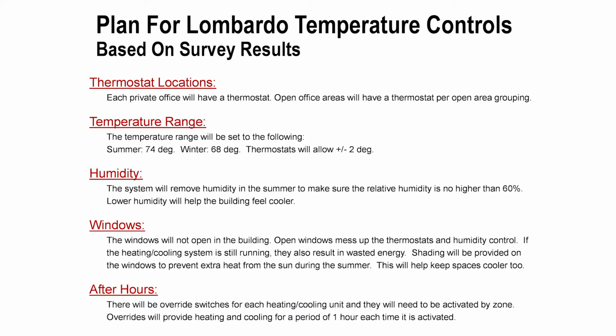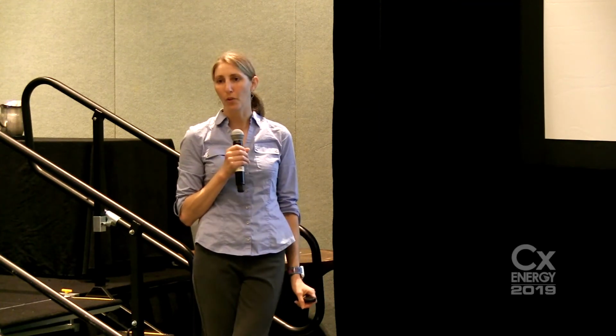So at that point we went to the thermostat in every office and agreed to temperature set points of 74 degrees in summer and 68 in winter. What's interesting is they made it through their first summer and commented that the building actually felt almost too cold at 74 — something they hadn't expected, since they were worried about 74. It turned out the amount of dehumidification occurring in the system kept the air feeling much cooler than expected, and some people almost got too cold and were bumping it up. We allowed them a float of plus or minus 2 degrees on their own thermostats.